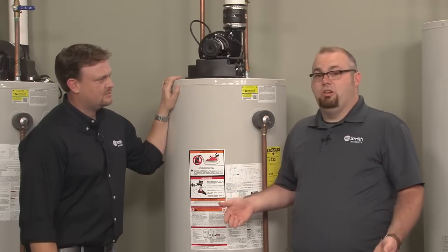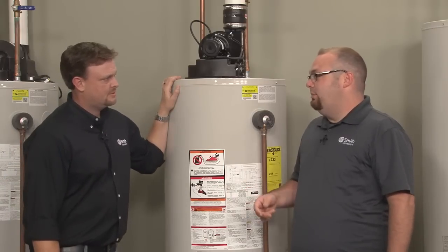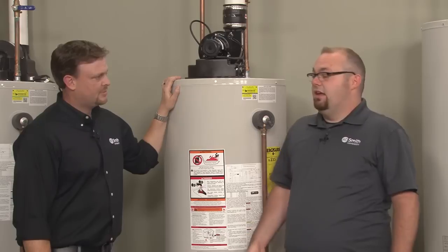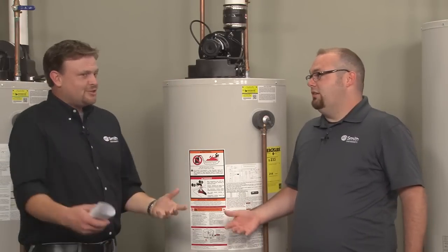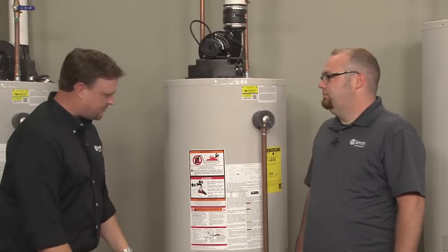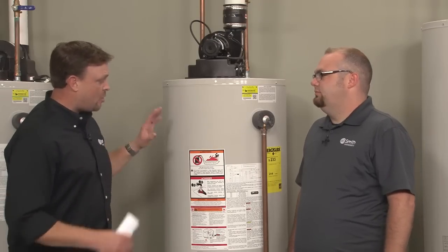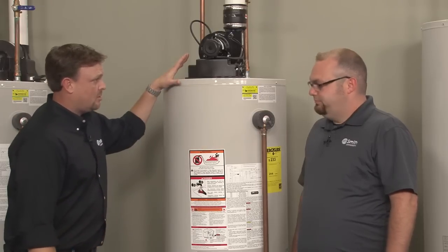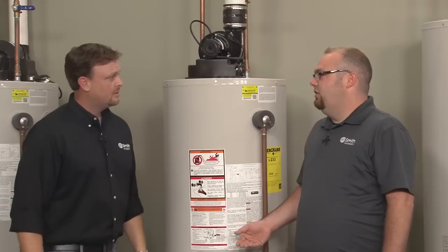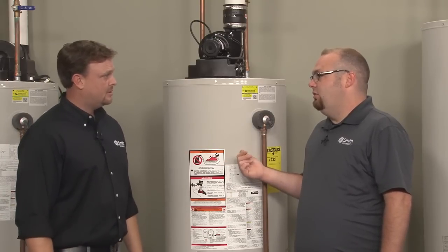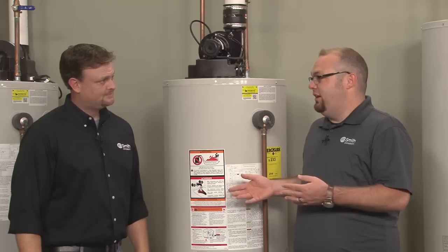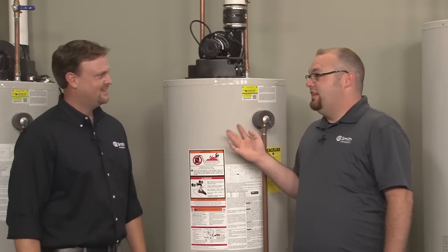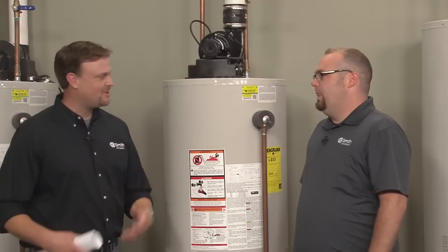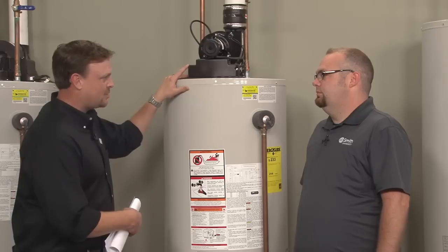So first thing you want to check is if the blower motor's running. If it's Honeywell, cycle power off, turn it back on, see if the blower starts. On the IntelliVent, if the blower's running, you'll just see it running. You would hear it and see it running. So that's the first thing to check. So I come up there, I turn it off, turn it back on, and on a Honeywell, I'm going to be listening for that blower to kick on. And what if it doesn't kick on? If it doesn't kick on, the first thing I do is change the blower capacitor on the Honeywell, because capacitors can fail. It's very rare, but most of the time if an electric motor doesn't start, it's the capacitor. Right. And since this one's separately replaceable, replace the capacitor. So if it doesn't start, I'm going to go ahead and replace that capacitor, and then it should start.